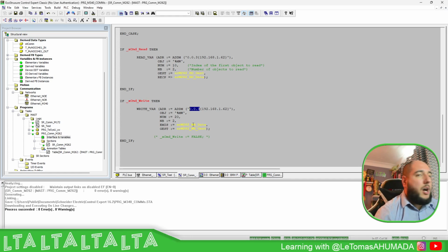The important thing is how you execute them, how you use it. I can easily delete this if condition and just trigger, okay, but that will probably overload the communication channel of the M340. That's why it's important to have a sequence if you're working on this, or probably use a NOC card or a NOE card, so you can use the IO scanner. That would probably be the best.